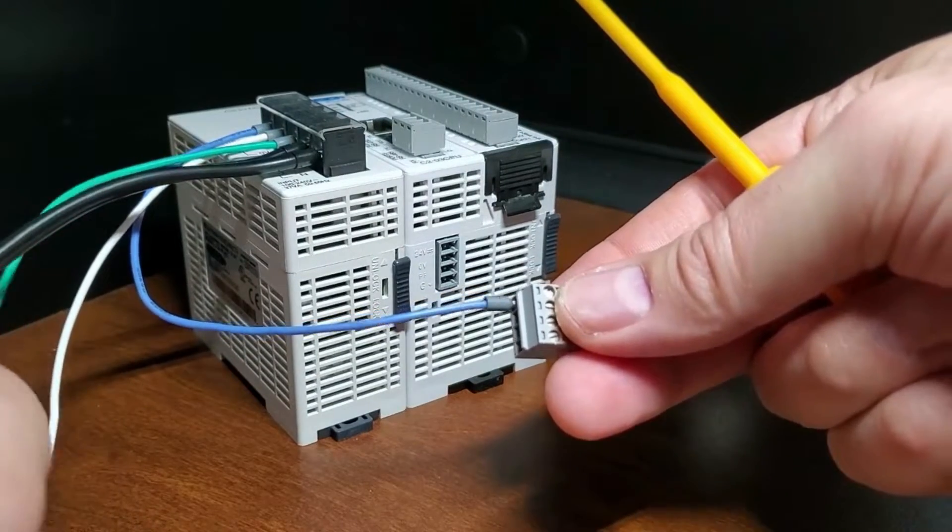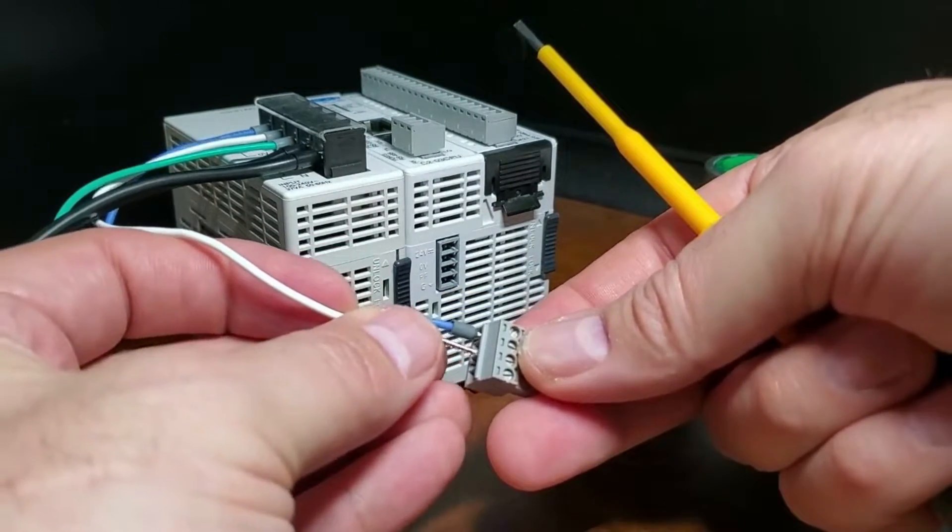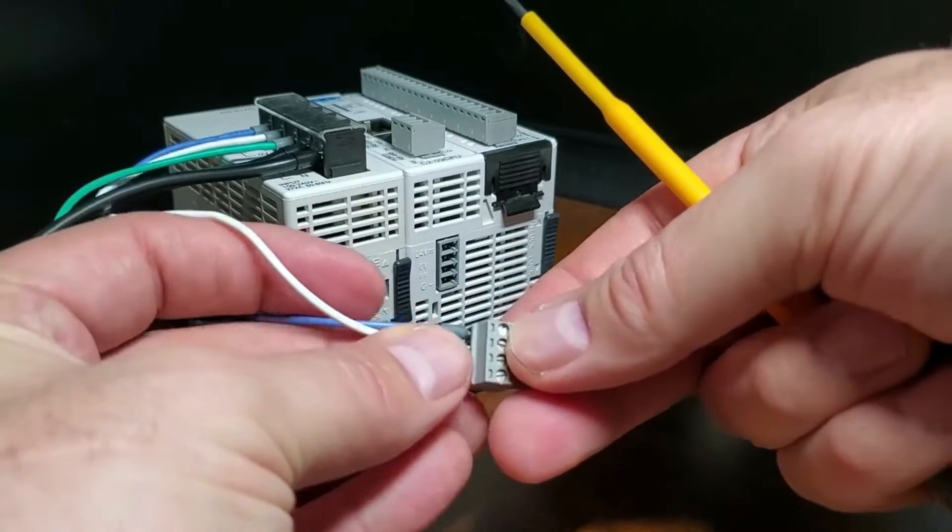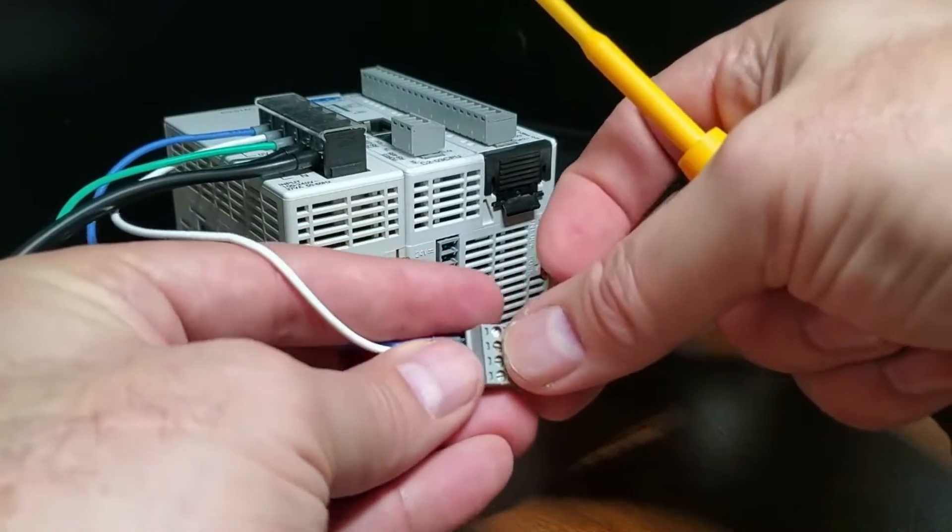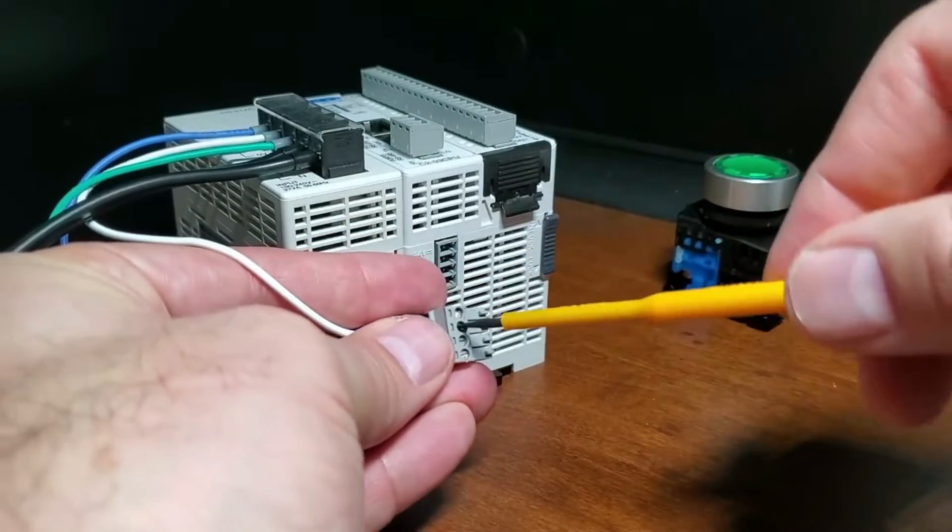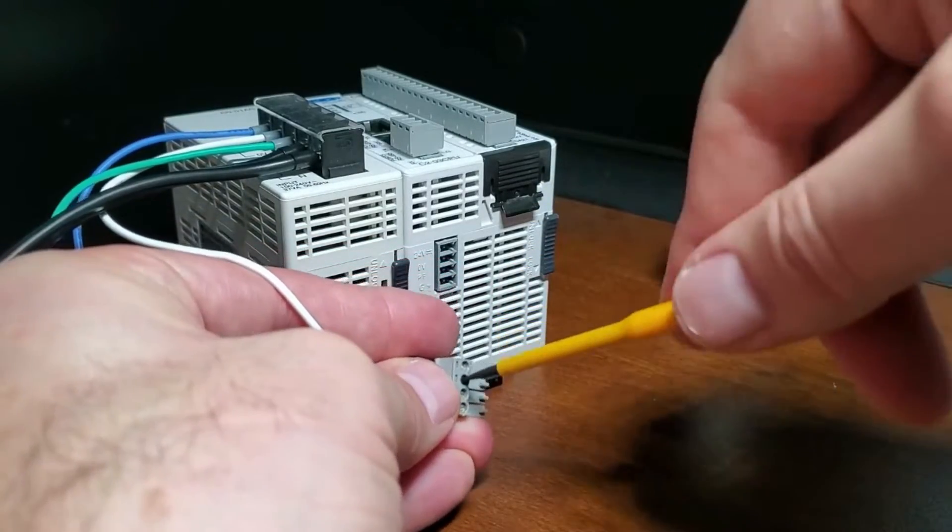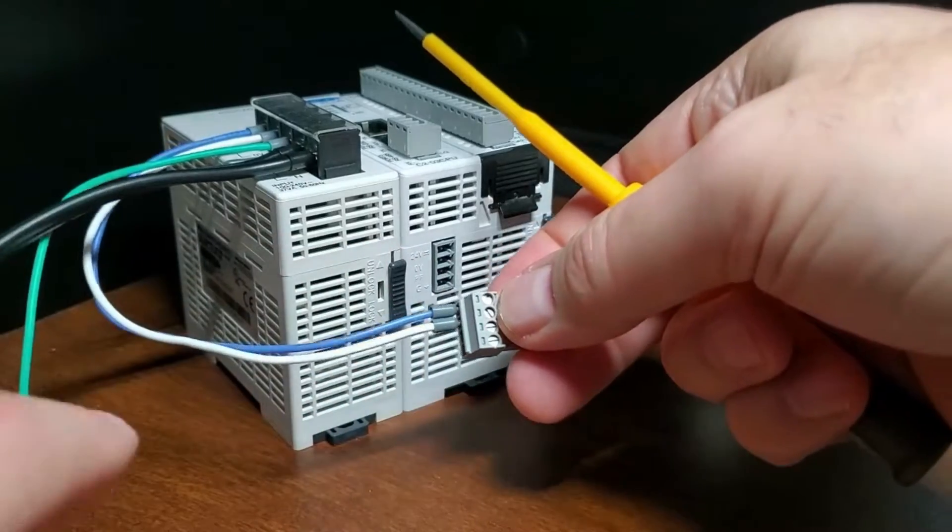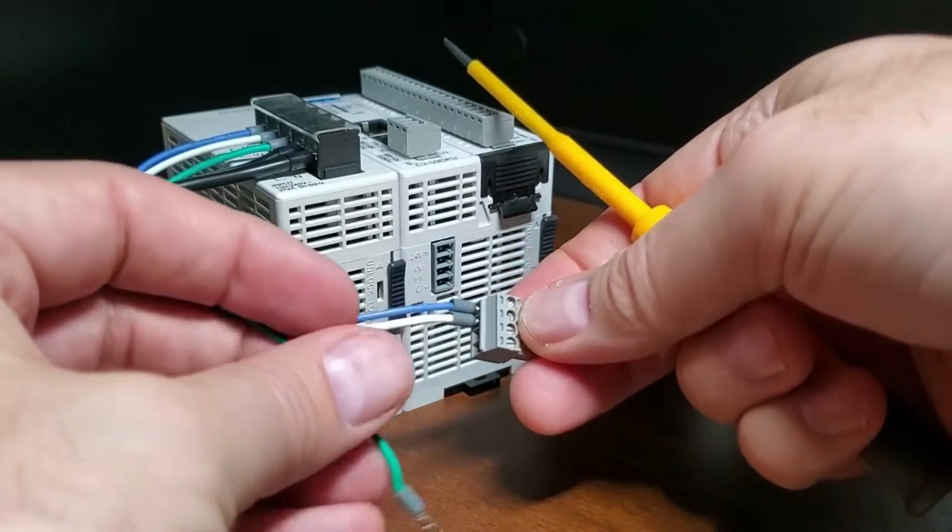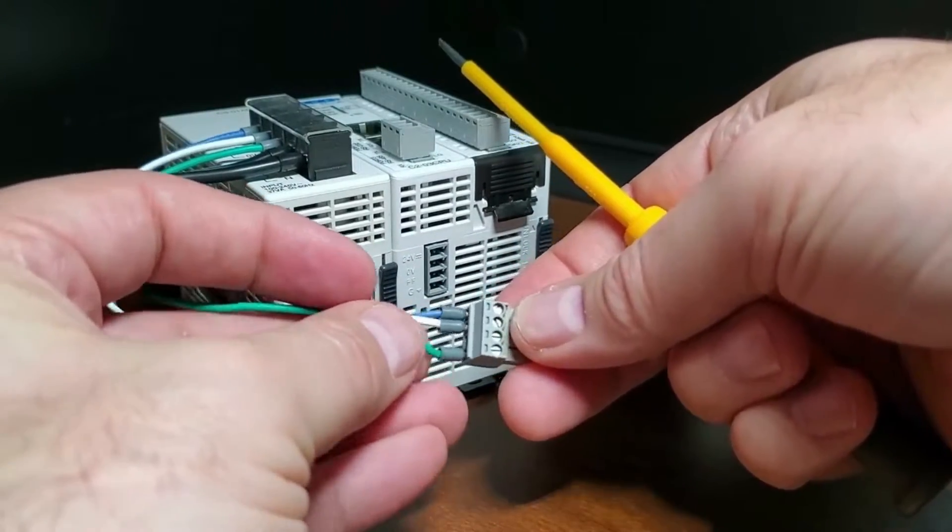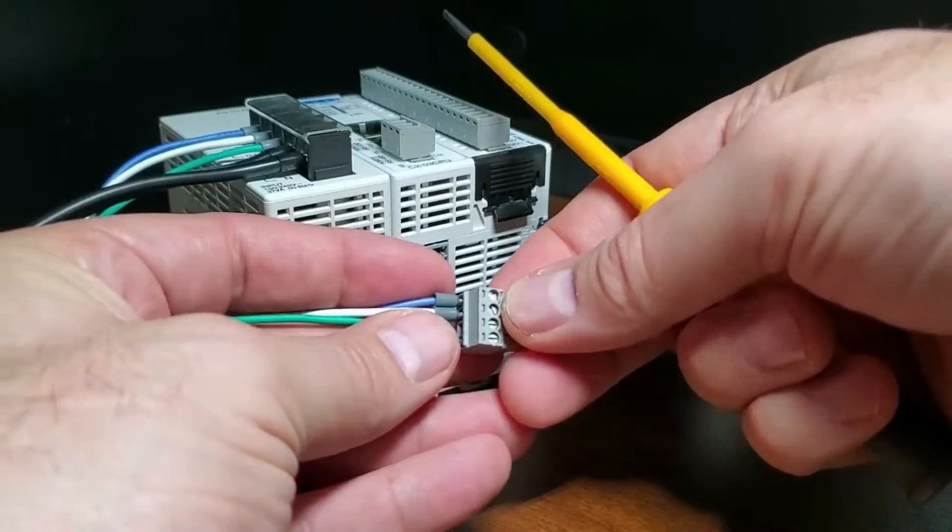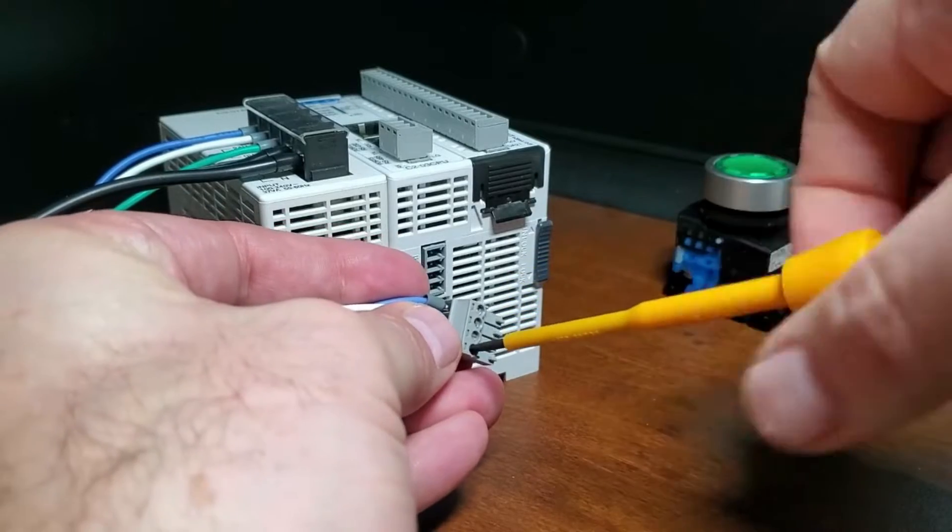The second area is the power required by all externally connected I/O devices. This should be viewed as the field-side power required. The field-side power depends on the voltage used for a particular input or output device as it relates to the wired I/O point and on the calculated load rating of the connected device.